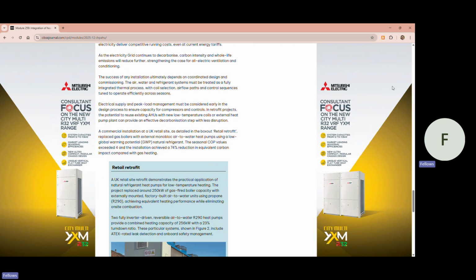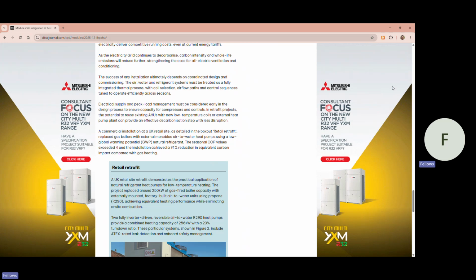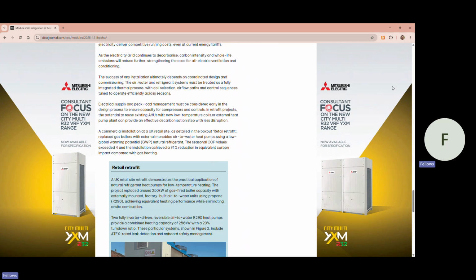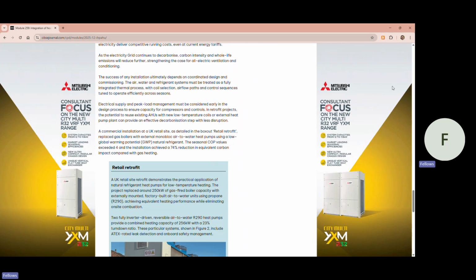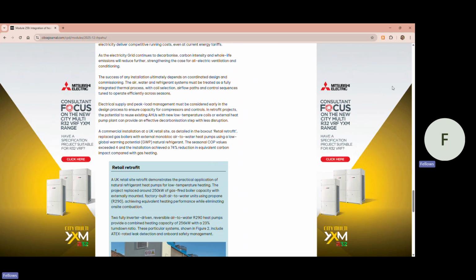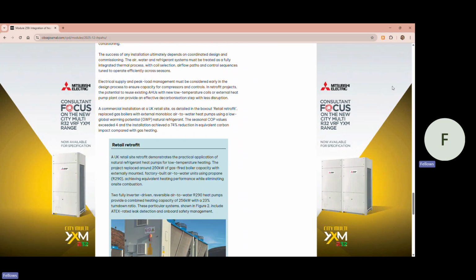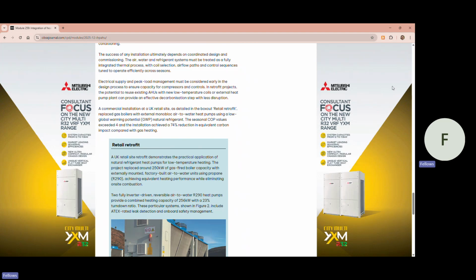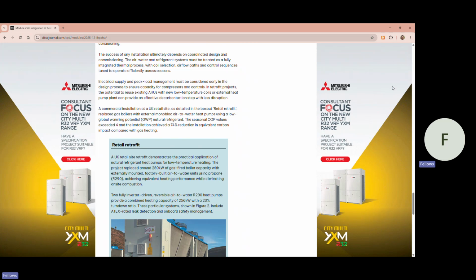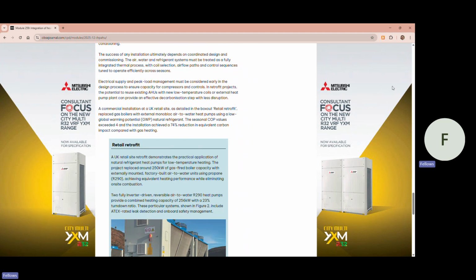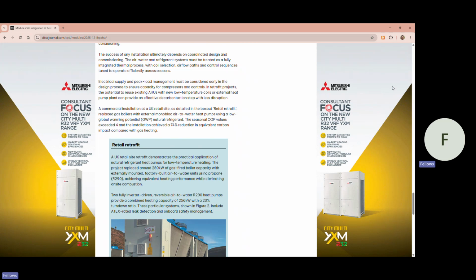Electrical supply and peak load management must be considered early in the design process to ensure capacity for compressors and controls. In retrofit projects, the potential to reuse existing AHUs with new low-temperature coils or external heat pump plant can provide an effective decarbonisation step with less disruption. A commercial installation at a UK retail site, as described in the box-out retail retrofit, replaced gas boilers with external monoblock air-to-water heat pumps using a low global warming potential, or GWP, natural refrigerant. The seasonal COP values exceeded 4, and the installation achieved a 74% reduction in equivalent carbon impact compared with gas heating.